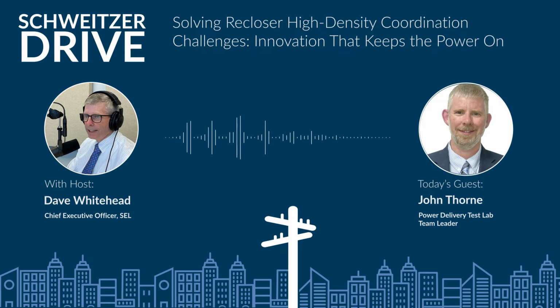So we're talking about that 3,000 customer feeder, and we want to break it into 300 customer blocks. That's 10 reclosers we have to stack. The reality is the traditional way of coordinating things with just time-based coordination, you don't have enough room. By the time you take all these devices and make the furthest one down the line the fastest, and each one up the line a little slower, by the time you get back to the substation, your first recloser is tripping unacceptably slow, to where it's compromising the integrity of the system, possibly safety and all kinds of things.